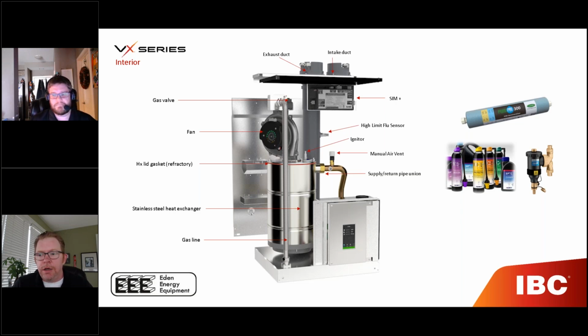We wanted to point out water quality because even if the boiler hasn't failed, less than the thickness of a dime of scale knocks 10% off your fuel efficiency. So it may not fail, it might just work like crap because somebody couldn't be bothered to hook the PuroPal to the garden hose before filling it. We're trying to make this super easy.